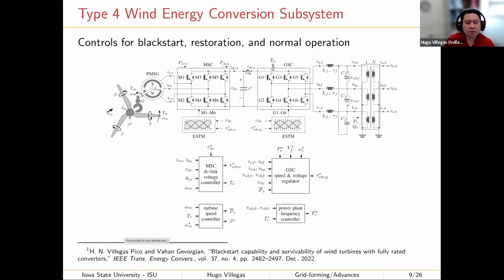We also have the machine side converter. The mission of this machine side converter is to regulate the DC link voltage, which in fact transfers power from the permanent magnet synchronous machine into the DC link. The typical reference frame we use is the synchronous reference frame. We also have the turbine speed controller, whose mission is to control the speed of the wind turbine. The speed is achieved by controlling the pitch angle of the wind turbine blades. And as I was mentioning before, we also have a power plant frequency controller, which sends dispatch commands to the grid side converter controllers.